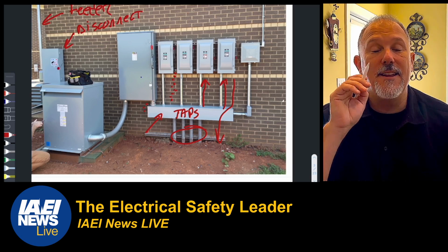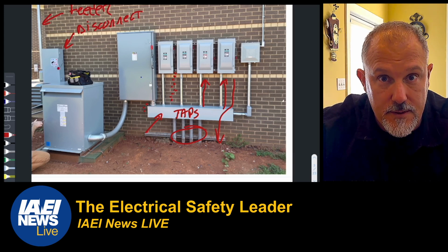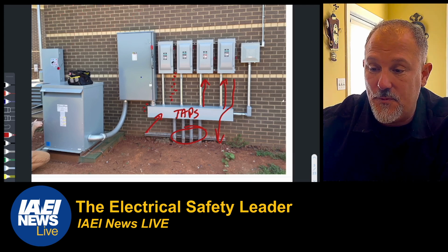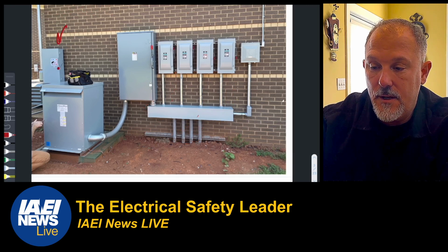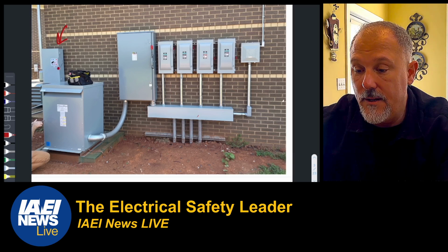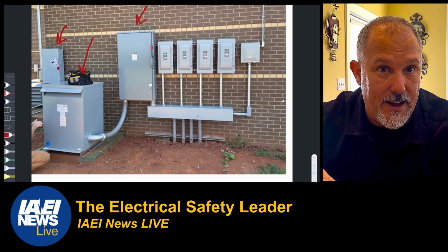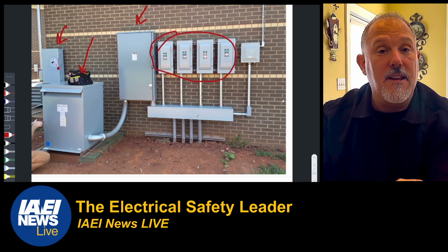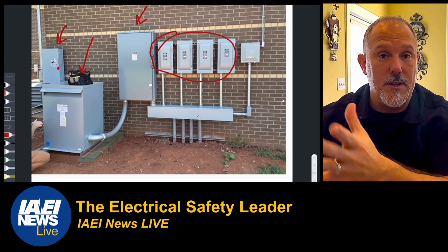Now, another thing that I really like about this application is that it is a tale of the times. Just look at the equipment that is in this application. We have one manufacturer's disconnect switch on the primary of this transformer. We have a different manufacturer's transformer. We have yet a third manufacturer's fusible disconnect switch on the secondary of that transformer, and then yet a fourth manufacturer of the disconnect switches that are going to each of the units that this is serving.